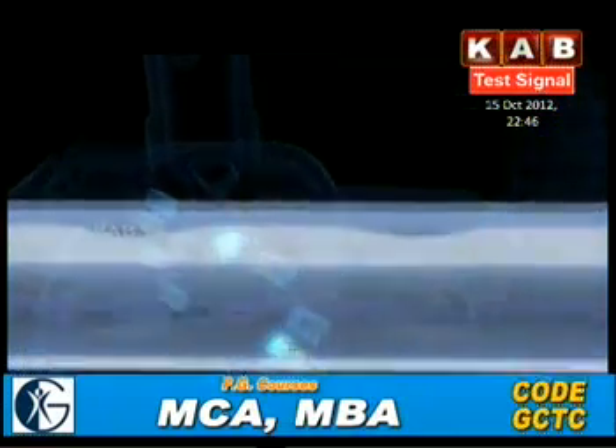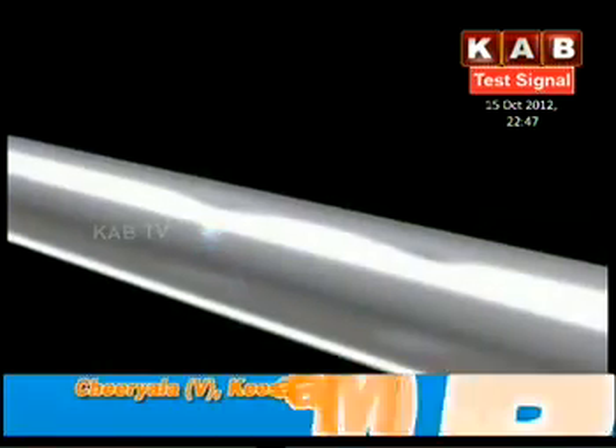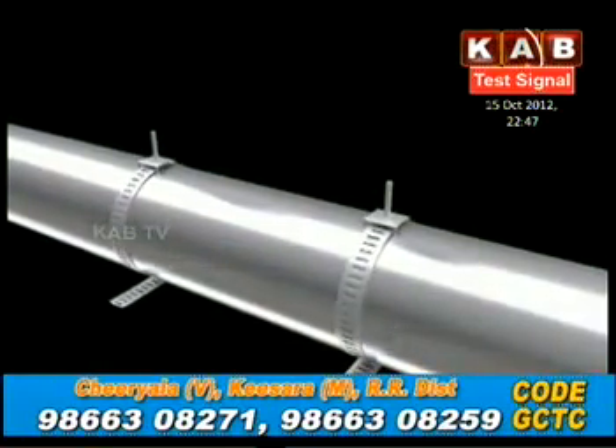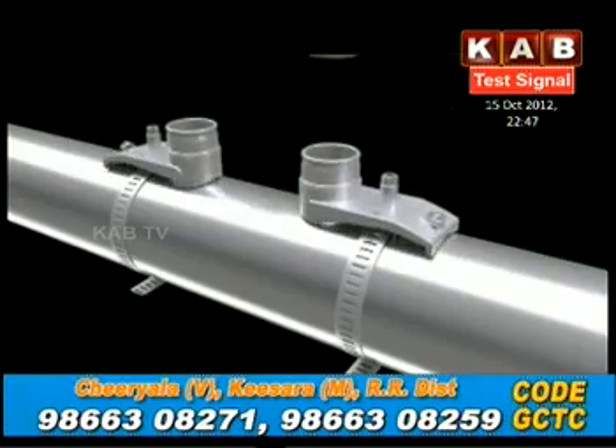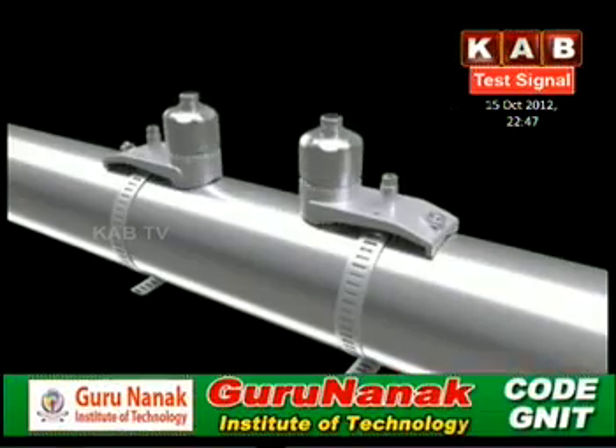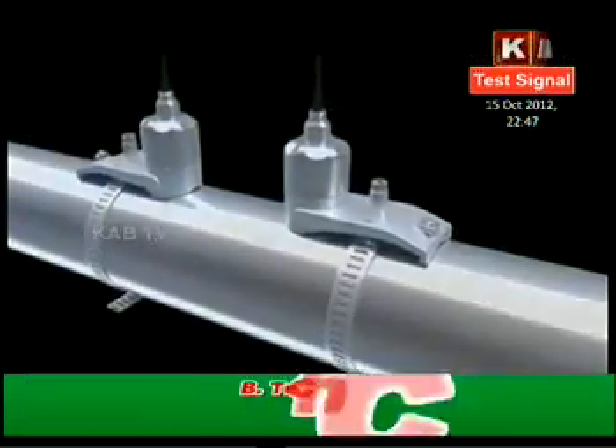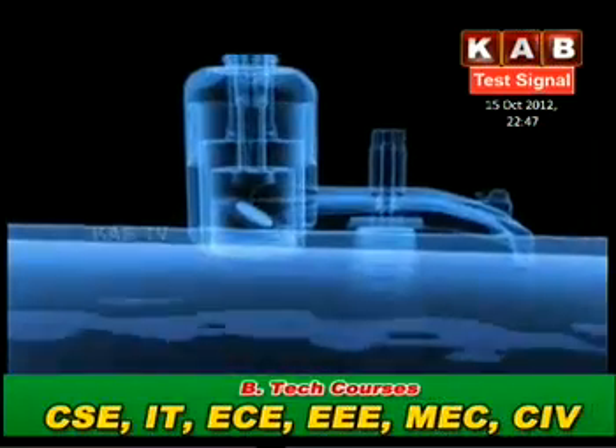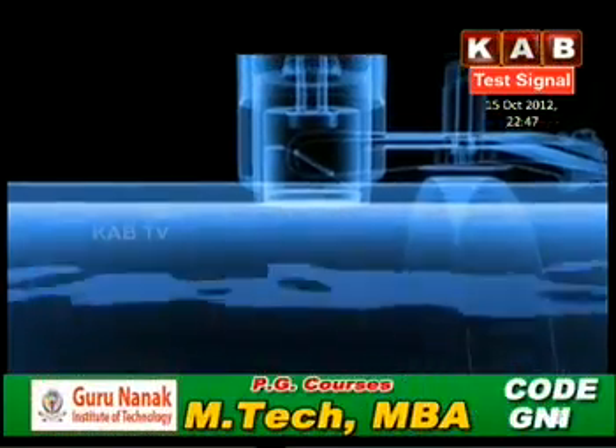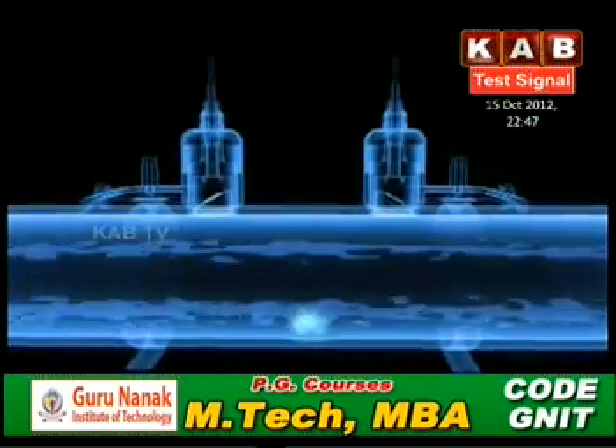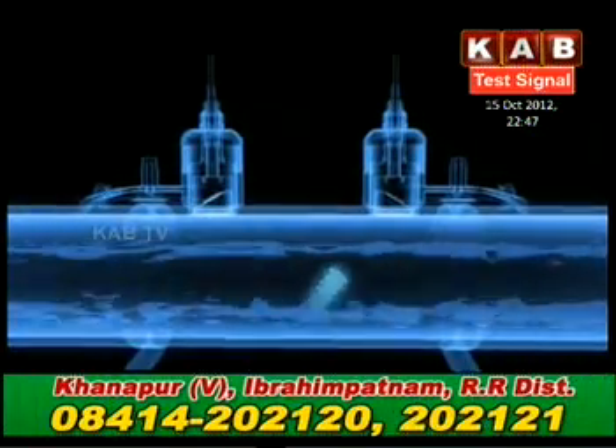For ultrasonic flow measurement, the sensors do not necessarily have to be fitted into the pipe wall. With a clamp-on system, for example, the sensors are fastened directly onto the outside of the pipe. They can be retrofitted at any time without interrupting the process. With clamp-on sensors, the ultrasonic signal is passed directly through the pipe wall and into the fluid. The signal continues through the fluid, is reflected on the opposite pipe wall, and then measured by the second sensor. In this example, with a 2-traverse installation.